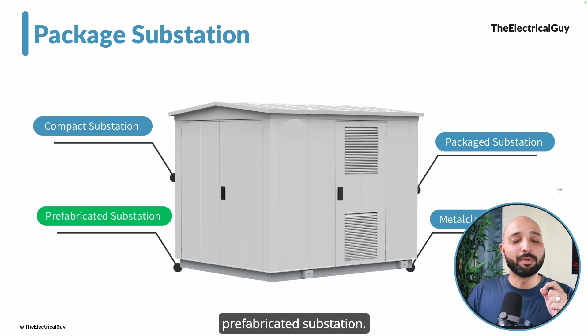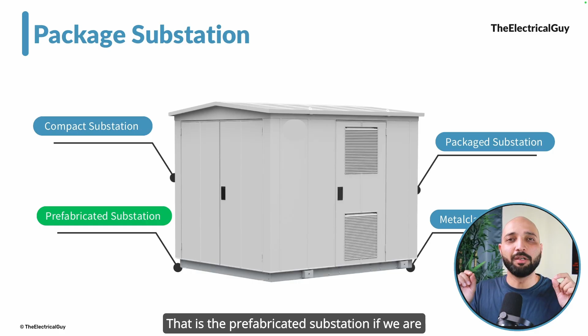First, let us make one thing very clear. This package substation has many names. Some people call it package substation, PSS. Some call it compact substation, CSS. Some also call it metal clad substation or metal clad distribution substation, MDS. But the actual name, the one used by the IEC standard, is the prefabricated substation. So don't get confused if people use different names - just remember these are all different names for the same thing, the prefabricated substation, if we're referring to the IEC standard.